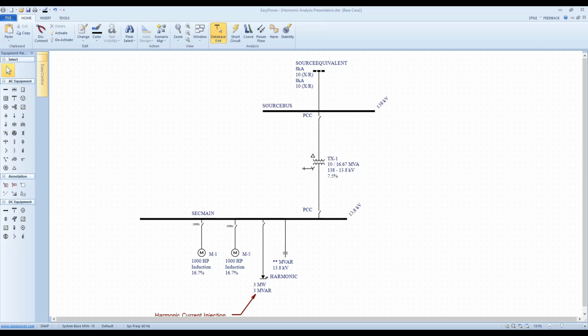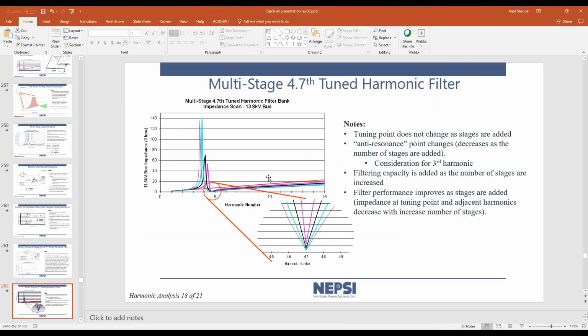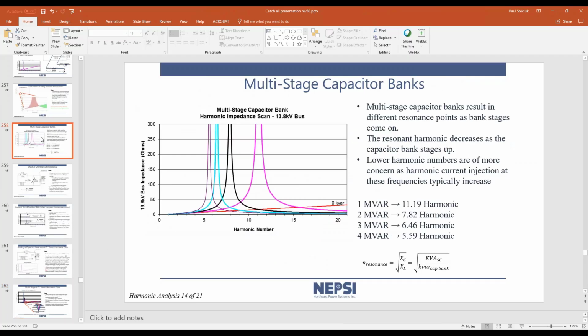And Syed has a question that says, as the resonance point changes with the change of the network topology, specifically when you're switching banks of capacitors, how do you decide the exact notch frequency or harmonic filter frequency? So this is a multi-stage cap bank, and in this situation, you can see there's a zero line. This red straight line represents the impedance of the network before capacitors are added to it, and then this purple line represents 1 megavar. The black line represents 2 megavars, the bright blue represents 3, and then purple is 4 again.